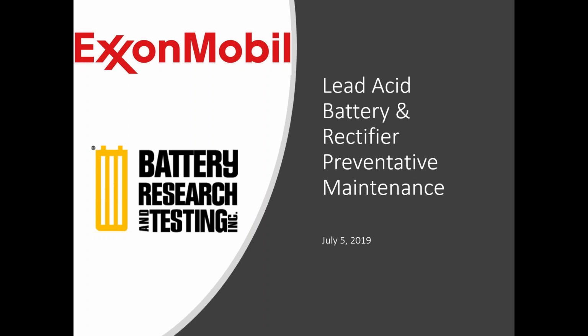The problem is some of those equalization circuits have timers on them, and timers don't always work properly. Sometimes they're manually put into equalization with the idea that you have to knowingly take it back out. Flooded batteries and NiCad batteries, some of those other flooded technologies, are more resilient to withstanding high charge rates in case someone forgets or a timer fails. Valve regulated, it's a death sentence. So that's probably why they have the notes in there.